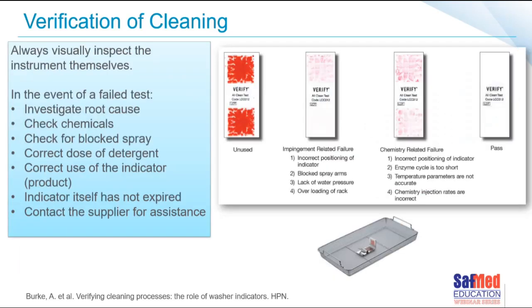It is very important to verify cleaning. Always visually inspect the machines and the instruments themselves. In the event of a failed test, investigate the root cause — look for blocked spray arms, check that the correct dose of detergent is being dosed correctly, and you may need your service provider to assist. Also check that the indicator itself was used, stored and not expired correctly. If a cleaning indicator shows only one side has come clean, it may be an impingement-related issue; if the entire indicator has changed colour but not correctly, it may be a chemistry-related issue.